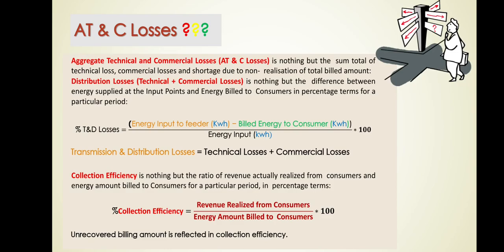That 50% includes technical losses as well as non-technical losses — for example, when consumers refuse to pay or engage in malpractices such as power theft. So total losses are made up of technical losses and non-technical losses together, which form the AT&C loss. We are going to discuss this and eliminate these losses so that revenue recovery increases — that is the main objective behind energy conservation thinking around AT&C losses.